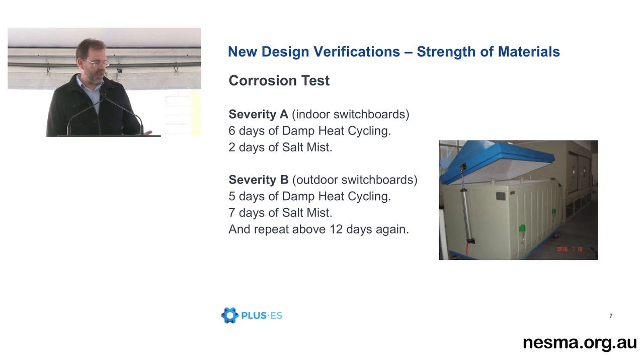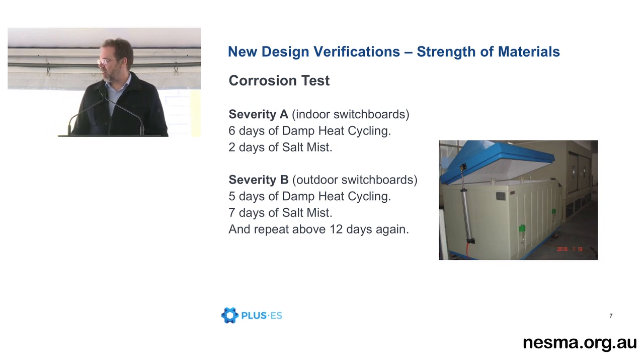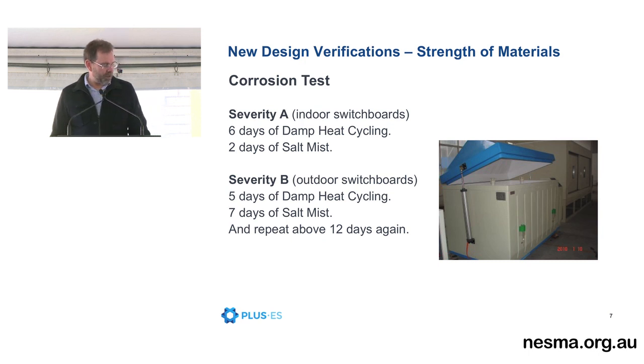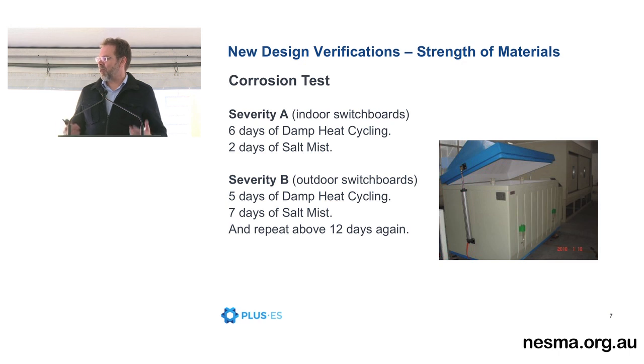As you can see, severity A is basically 8 days of testing in 2 chambers, and severity B is actually 24 days. It's amazing how much corrosion you can impart on some metal in 8 days. I've seen some corrosion samples come back, and you go, gee, I can't believe that happened so quickly. And I was talking to someone earlier, and these new tests actually introduce new conflicts.